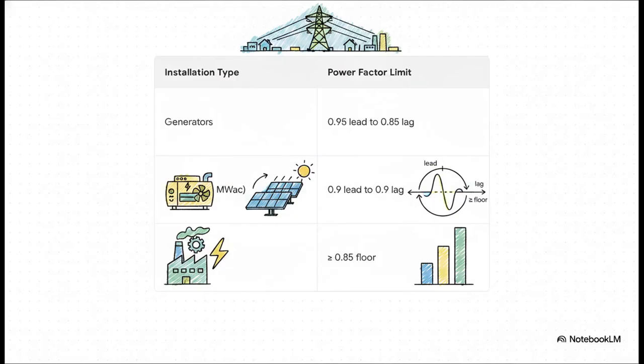Now, the regulatory rulebook actually explicitly defines these power factor limits based entirely on your installation type. For instance, generators have to maintain a capability of 0.95 leading to 0.85 lagging right at their terminals. Got a grid-connected solar plant of a megawatt or larger? You're operating between 0.9 leading and 0.9 lagging. But for high-voltage consumers, there's a hard floor of 0.85, and let me tell you, this is the one that catches people out all the time.